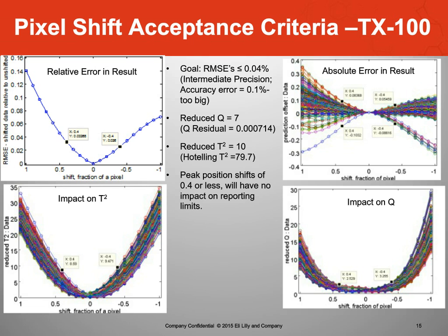How does that impact T? So remember our acceptance criteria for Q and T is 7 and 10. So for T, I want to be less than 10. So if I have a pixel shift of 0.4, I was getting just under 10. So that should work. So I'm good with that. A pixel shift of 0.4 would cause me to have a T squared of less than 10.